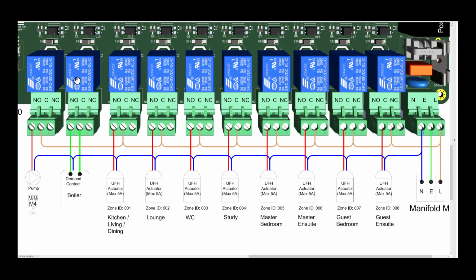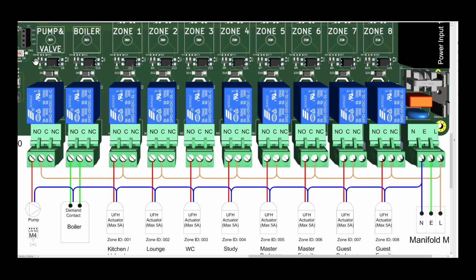Then we have another 2 connections. We'll bring it a bit up to see. So we have a boiler connection and a pump connection. Now again, it's a volt-free contact, so whatever your boiler demands, whether it demands a voltage signal or a volt-free signal, you can use it over here. Standard UK boilers have an option to connect a volt-free contact to it, and therefore you daisy chain C and normally open on this relay between all wiring centers from one to the other, and then you take it back to the boiler. So if any wiring center is calling for the boiler to operate, the boiler will start.